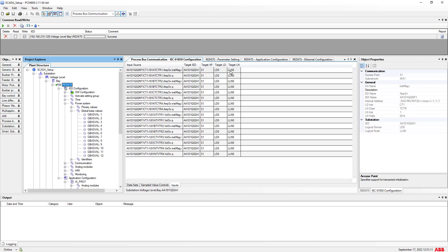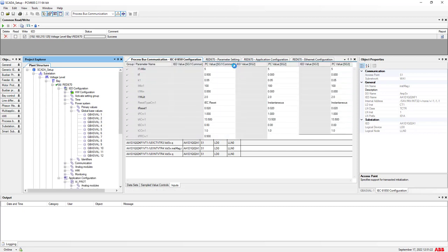And we go to the IED under test configuration by selecting the global base values, basically to see the CT and VT ratio. So here we have 220 kV in the primary and 110 volt. And then we have 1000 ampere in the primary. The units are on the right side.